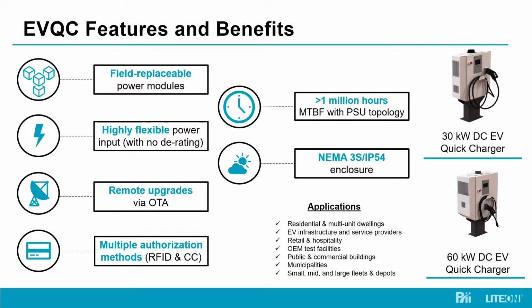Now, we don't expect an issue, as we're leveraging the same power conversion topology that exists in the data center today, which has a demonstrated greater than 1 million hour MTBF on that power supply topology. But you'd still be able to continue monitoring what's occurring in those modules in the field, and if there are any issues, we do have field replaceable modules.